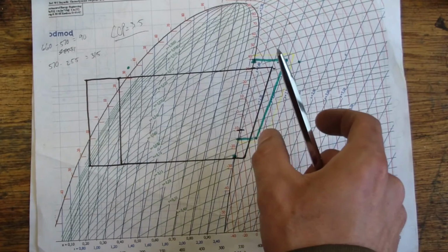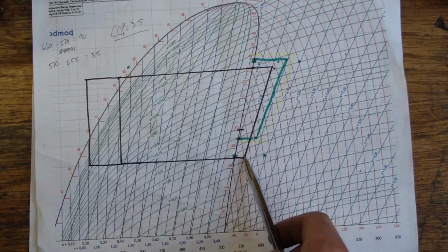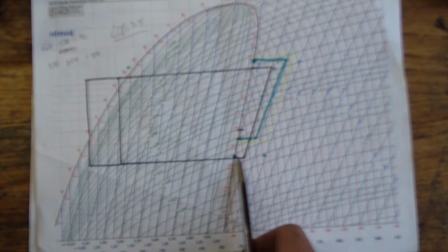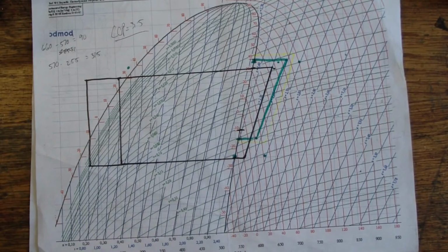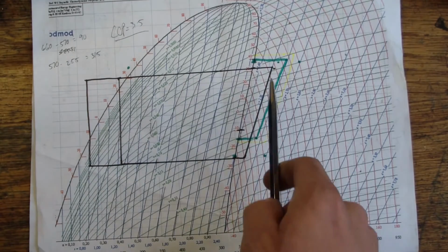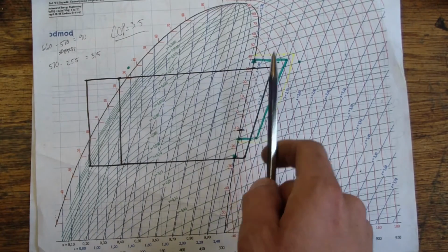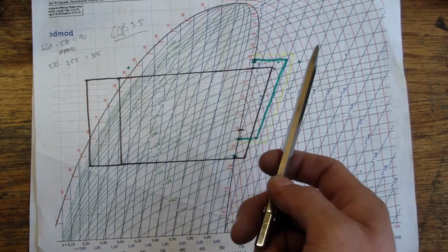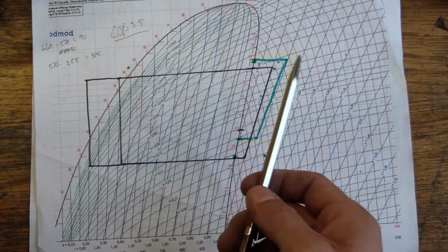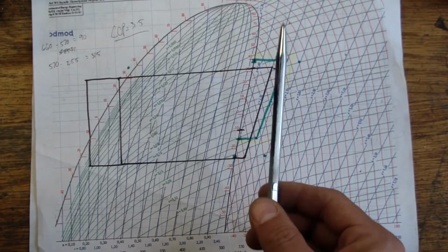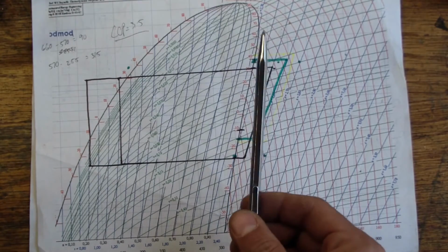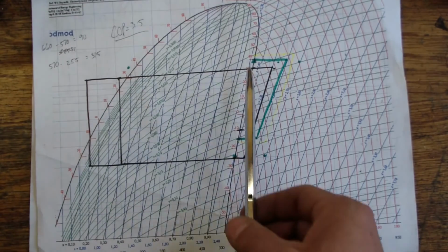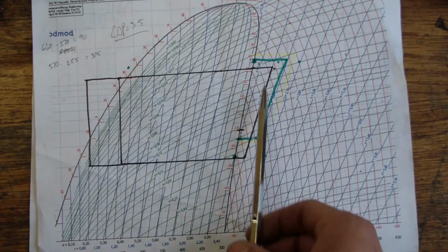Now, the actual amount of work that was done is still essentially from that point to that point, the enthalpy from there to there. We don't want to include the superheat added after the evaporator. However, we also have to consider that heat needs to be rejected on the condenser side after the discharge of the compressor. So it's essentially taking up some of the capacity of the condenser to discharge heat. You want to use that condenser to actually do some condensing to more effectively discharge heat, because we work a lot better if we work off this latent heat and we don't work in the sensible heat area over here.